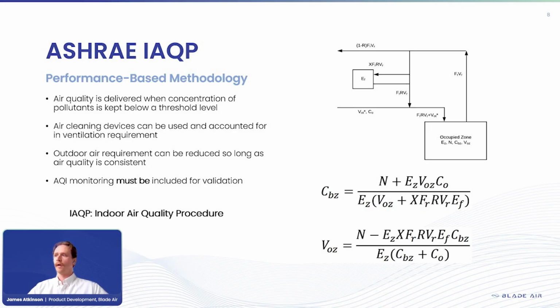Importantly, this allows us to actually account for the air cleaning devices in the design of our air systems, right? Normally with the VRP, the original one I showed before, you can add air cleaning devices and they may be a requirement if you're determined to have poor outdoor air quality in your area, but you can't reduce the size or the volume of your outdoor air. And that's all air that you have to treat, heat up, cool down, right? That's a lot of energy. With this, you can actually reduce the fraction of outdoor air to account for the fact that your air is being acceptably treated and recirculated.